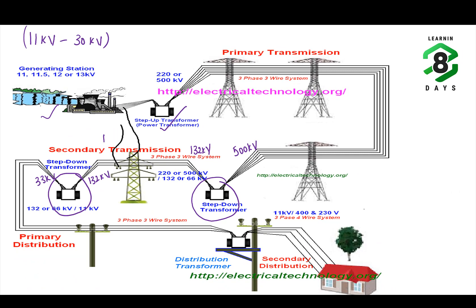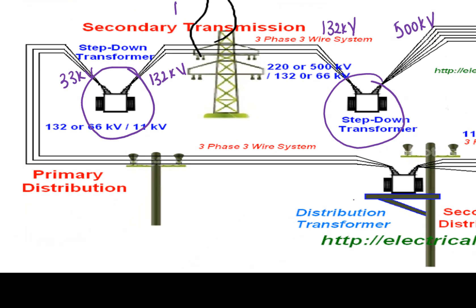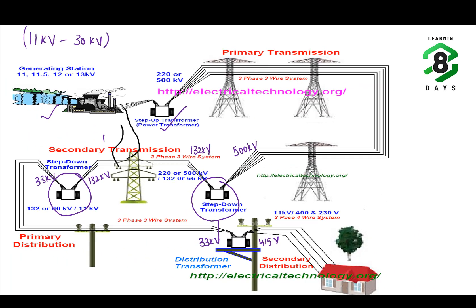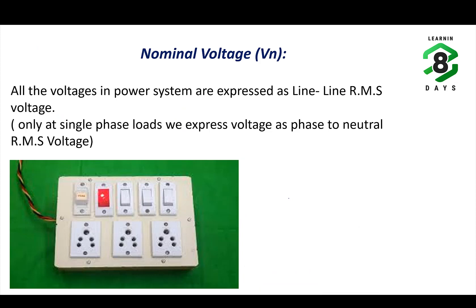After this stepping down, primary distribution starts. Primary distribution is carried by a three-phase, three-wire system. The voltage is stepped down again — for example, from 33 kV to 415 volts — and distributed at 415 volts to domestic customers. Industrial customers can be directly fed at higher voltages such as 132 kV or 33 kV, depending upon their requirement.